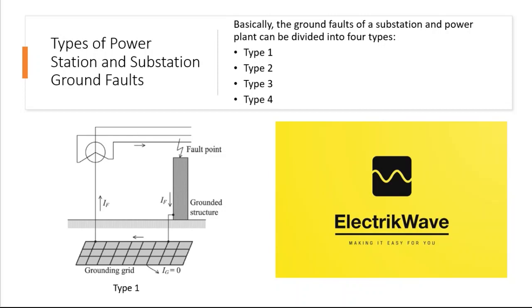Let's see Type 1 fault. Fault within local substation, only the neutral of the substation is grounded, and the fault current flows from the fault point through the metal path composed of the grounding grid. There is no current flowing into the earth.